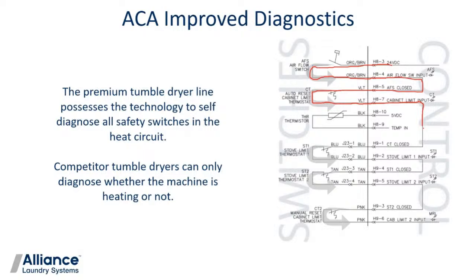Therefore, if we ever have a problem with one of these switches, we will generate an error code specific to that switch. Like it says in the bottom statement, competitor tumble dryers only diagnose whether the machine is heating or not. So it's basically an in-series circuit where we send this one signal out and it goes through all those switches in a row and then winds up at the gas valve. Well, if one of those switches has a problem, we have to diagnose that individually with a voltmeter, and we really have to know what's going on. So this is a commercial machine. It needs to stay running. This should help us immensely in our efforts to keep the machine running.